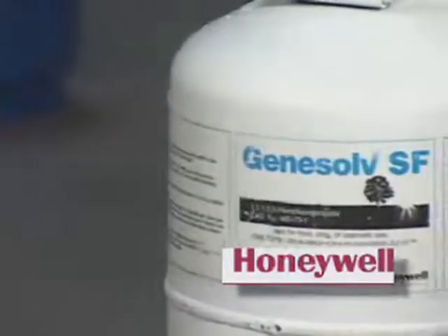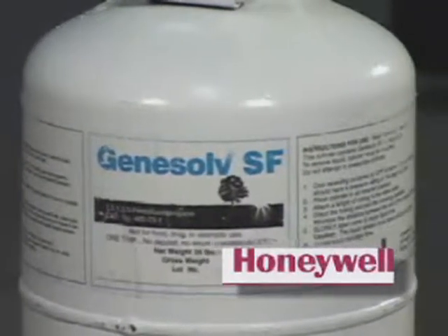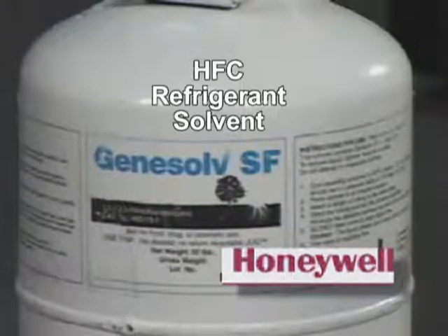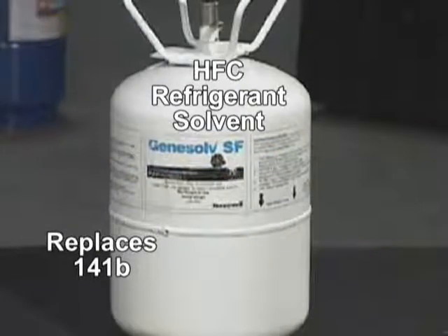The unit is specifically designed for use with the Genesolv SF flushing solvent from Honeywell Specialty Chemicals. Honeywell's Genesolv SF is an HFC refrigerant solvent that replaces 141B and works like R11. Its boiling point allows for effective liquid flushing and vacuum recovery.